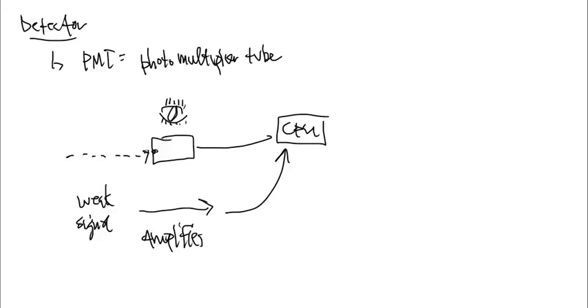So the photomultiplier tube basically does that job, and that's really what we're calling the detector. It sees the light that comes in, it distinguishes the difference of the light that's there before and after the sample is present, and then it relays that signal to the computer.